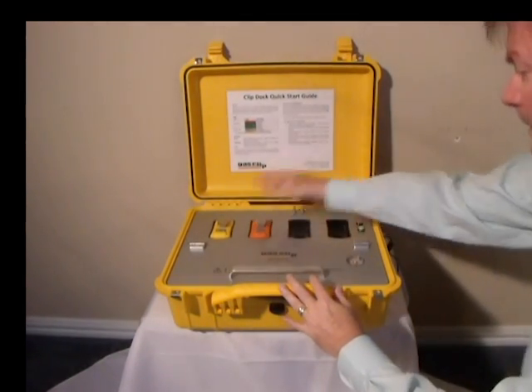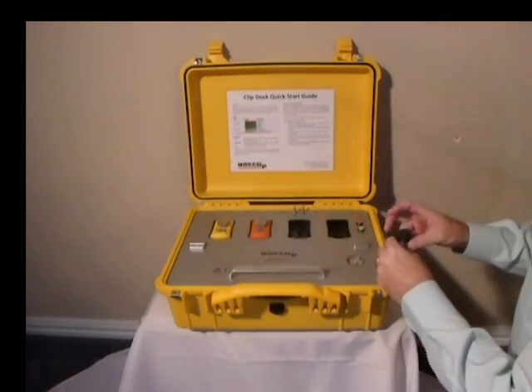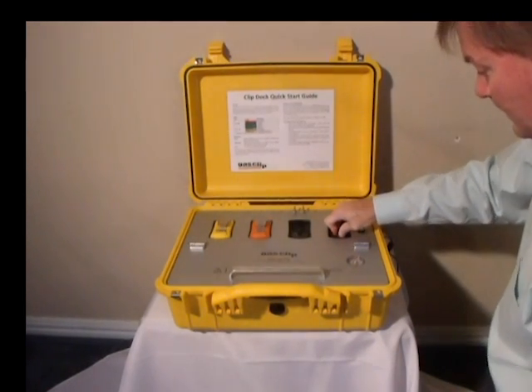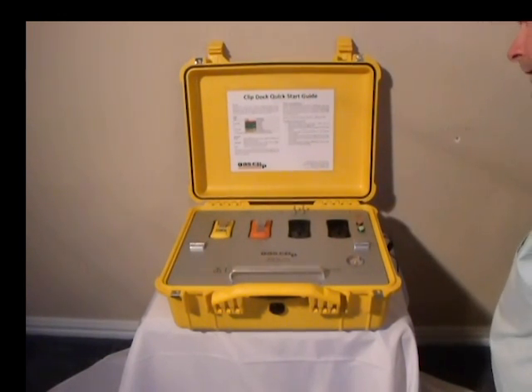To test your detectors, make sure they have been activated and place them face down on the Clip Dock. Use the rubber plugs in any cradles that don't have detectors, and connect a vent hose to the quick connect vent if so desired. Then push the red bump test button and the dock will begin the test.